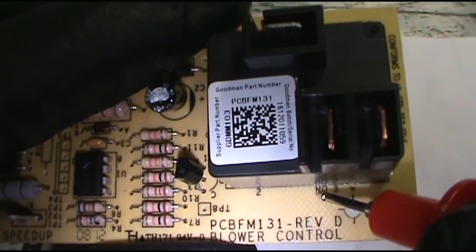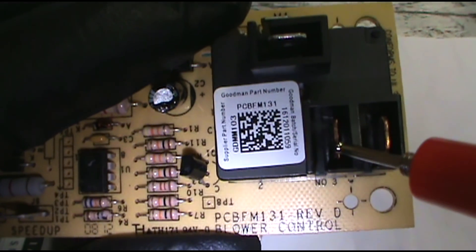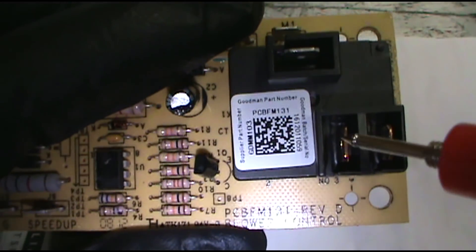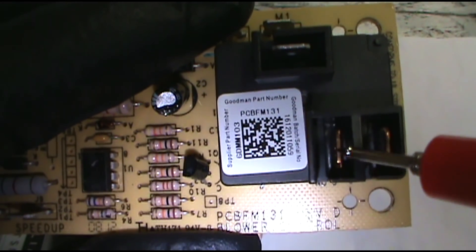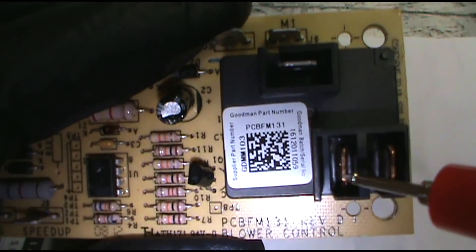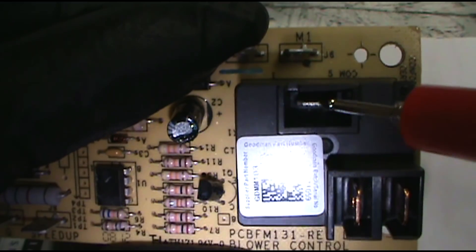And this here, NO, for this terminal here stands for normally open. This will be the power coming in, the 240 volts high voltage. So when it calls, it closes the switch and feeds power to the common and the fan comes on.